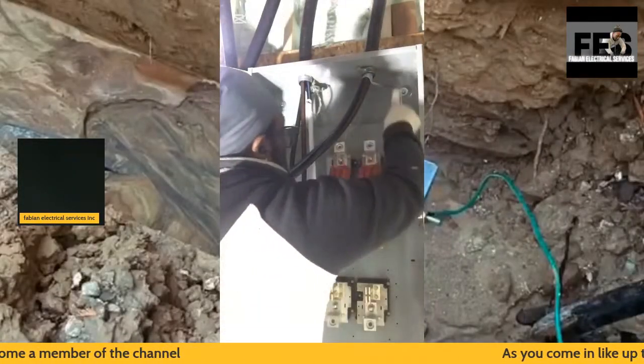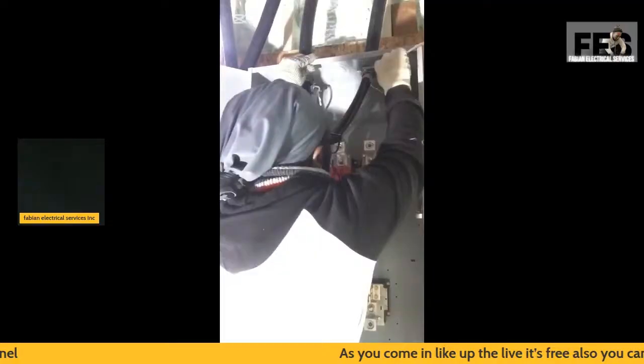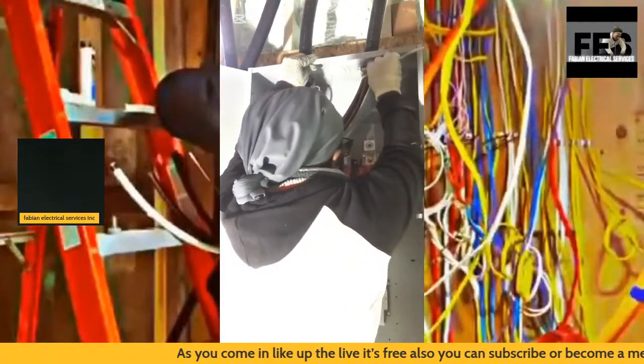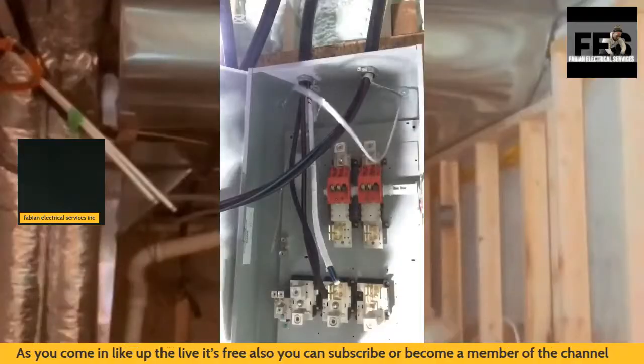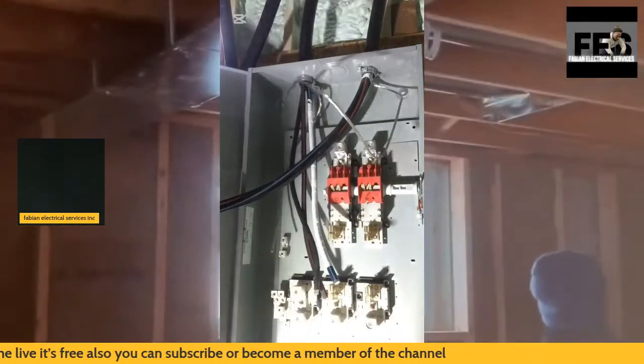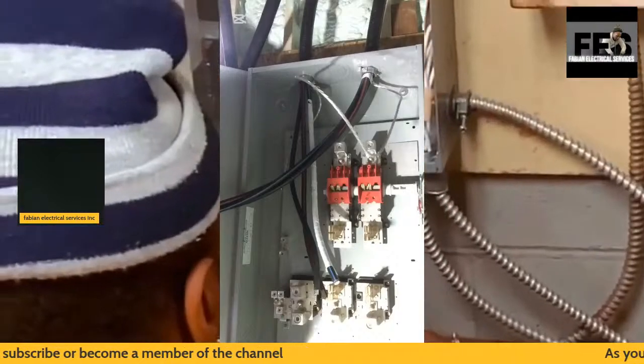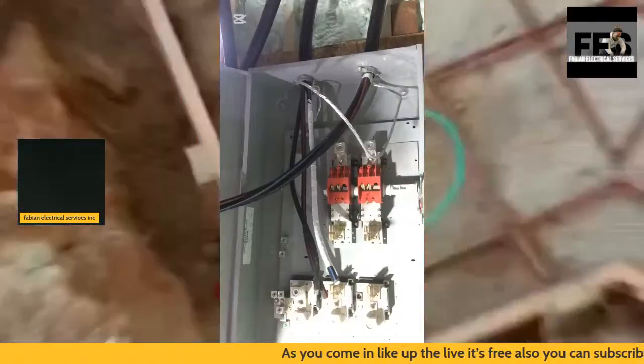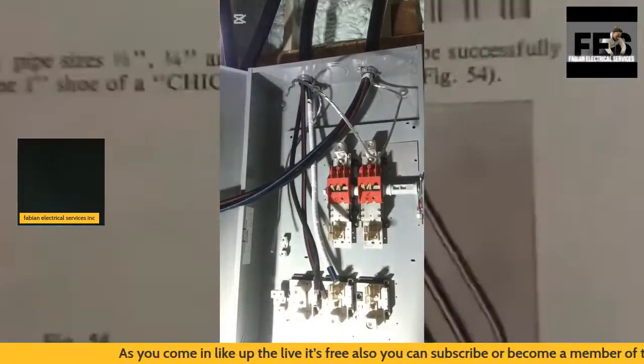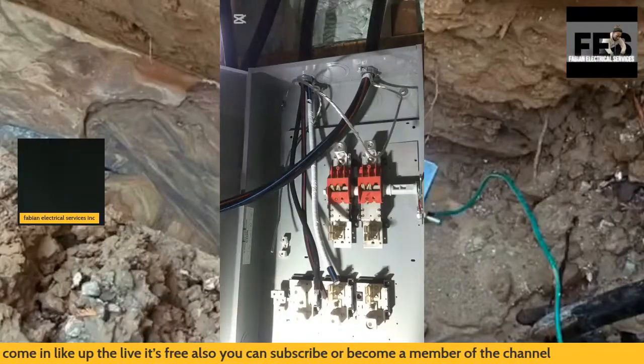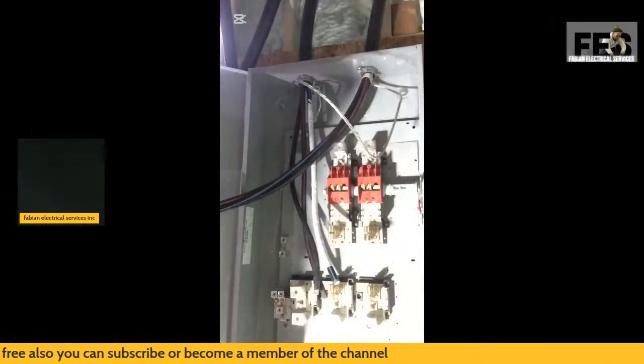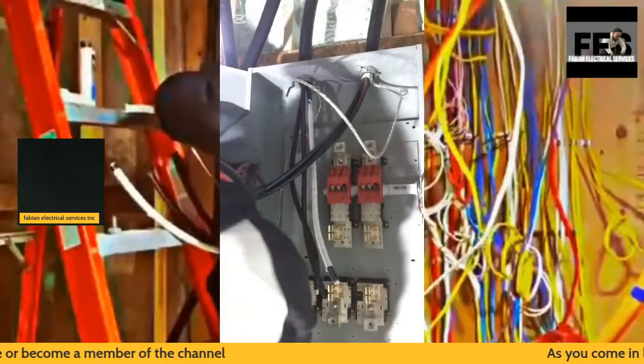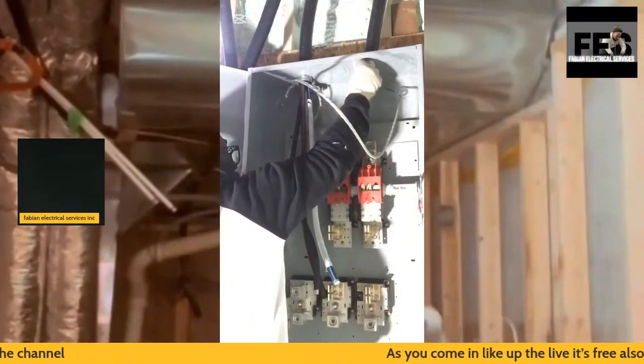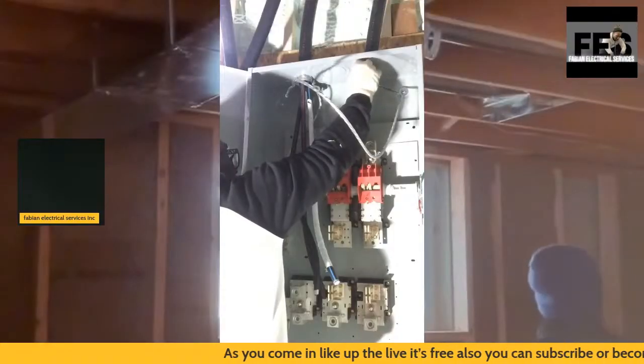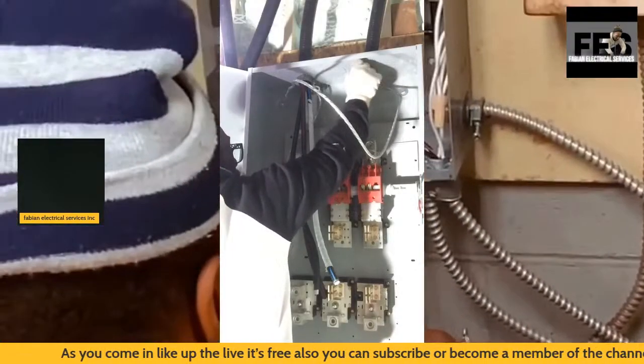Also, you're going to see I have my phasing tape on my cable. The reason is this cable does not come with an identified neutral, and the code book simply states that your incoming neutral has to be identified. There is an electrical code rule that states that for a particular size of cable we must identify up to. So this is what I am doing here, identifying my conductors with the white tape that is being used. It's always best to have your line and loads coming in separated.